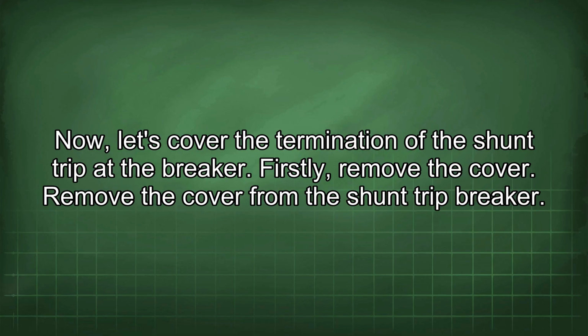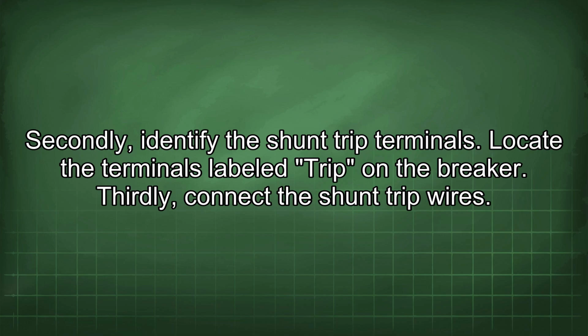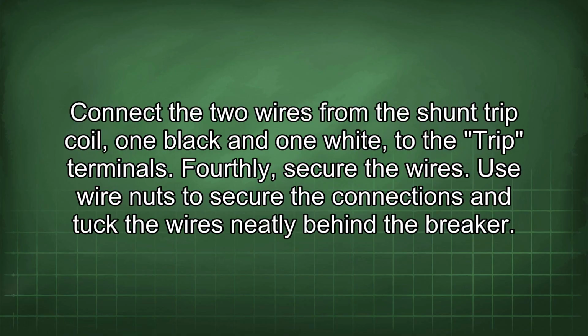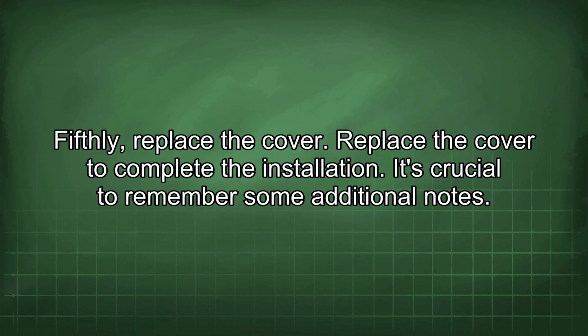Now let's cover the termination of the shunt trip at the breaker. Firstly, remove the cover. Remove the cover from the shunt trip breaker. Secondly, identify the shunt trip terminals. Locate the terminals labeled trip on the breaker. Thirdly, connect the shunt trip wires. Connect the two wires from the shunt trip coil, one black and one white, to the trip terminals. Fourthly, secure the wires. Use wire nuts to secure the connections and tuck the wires neatly behind the breaker. Fifthly, replace the cover. Replace the cover to complete the installation.